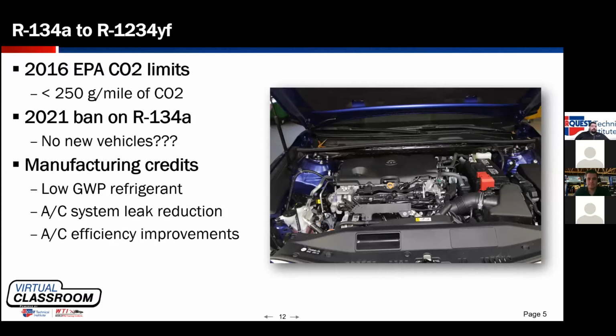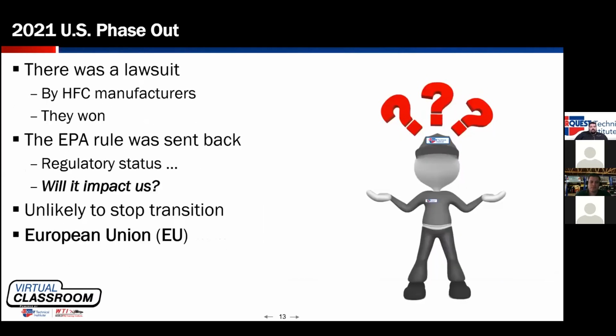Originally, there was going to be a phase out of R134A in new production vehicles for 2021 model year. That phase out originated in Europe, and part of the push for a low global warming potential refrigerant came out of Europe. European Union regulations pushed for a low GWP refrigerant starting for 2012 model year for new platforms and across the board for 2017 model year. In addition to that, Europe also started cutting back on the allowable imports of R134A, which is something we have not done in the United States. As it stands, that phase out is not currently happening.